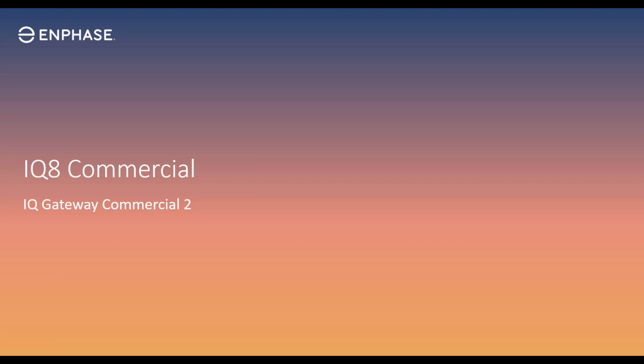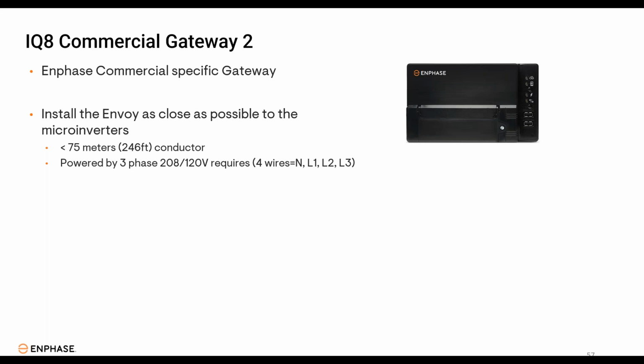The IQ Gateway Commercial 2 is specific to the IQ commercial microinverter. They look very similar to other gateways, so it is important that you are ordering the correct material and making sure you're taking the correct material out to site to install. The gateway needs to be powered by a 3-phase 208 volt, typically by a 15 amp breaker. We like it to be installed as close as possible to all the microinverters. So you can see it has a 246 foot of conductor length that it's sending that power line communications through. So the closer it is to all the microinverters, the better that communication will work.